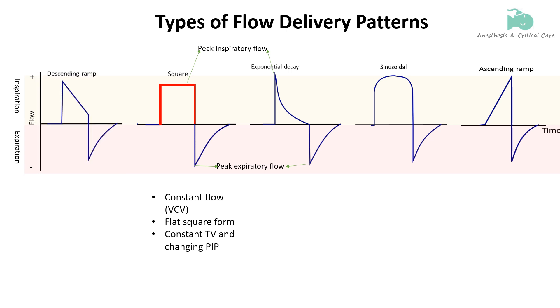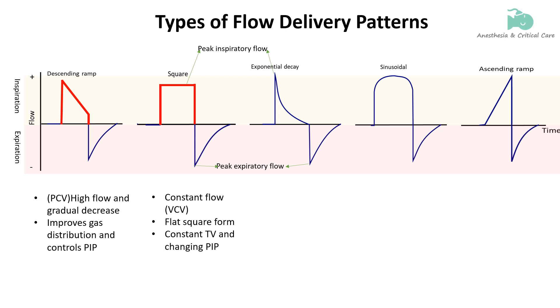The descending or decelerating flow waveform, seen in pressure-controlled ventilation and some volume modes, starts with a high flow rate that gradually decreases during inspiration. This flow pattern improves gas distribution and reduces peak pressures.